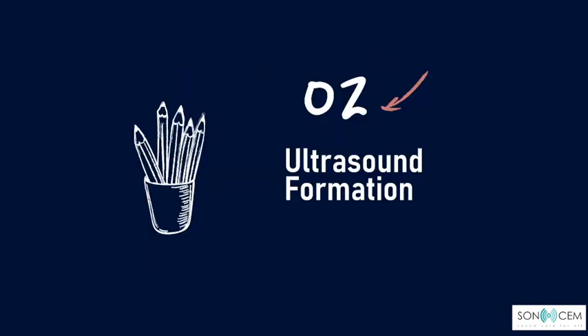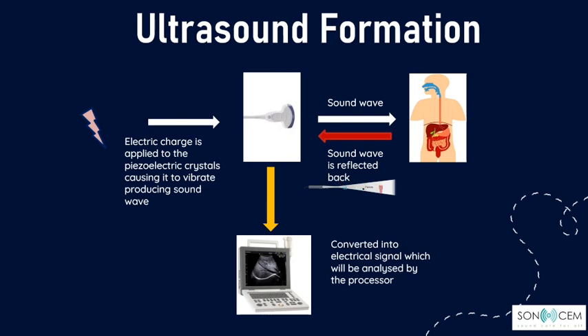Moving on to how ultrasound waves are produced. The probe acts as a sender and receiver. The electrical charge is applied to the piezoelectric crystal in the probe, causing it to vibrate, producing a sound wave. And this sound wave then travels through the tissue, where some of it is reflected back to the probe.